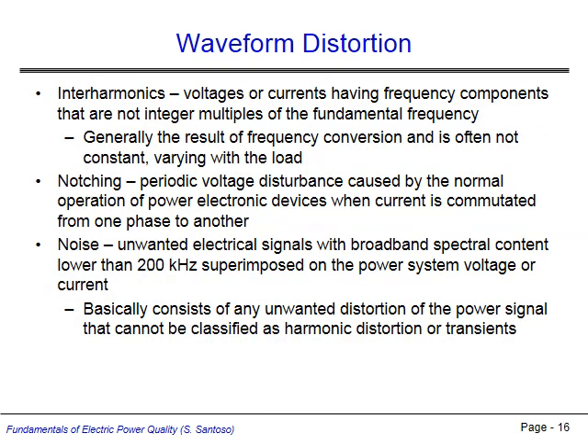Interharmonics are components of voltage or current waveforms that oscillate at a frequency that is not an integer multiple of the fundamental frequency. Interharmonics occur due to loads with frequency converters present in the system. Notching is a periodic fluctuation in voltage that is both sharp and brief, caused by switching functions in power electronic devices. Noise is electrical signals with broadband spectral content below 200 kHz that is superimposed on the voltage or current waveforms of the system. Noise is something of a catch-all term for unwanted distortion that cannot be classified into one of the categories previously discussed.